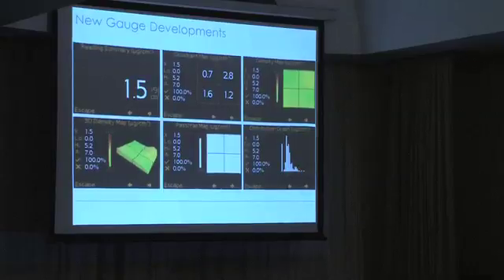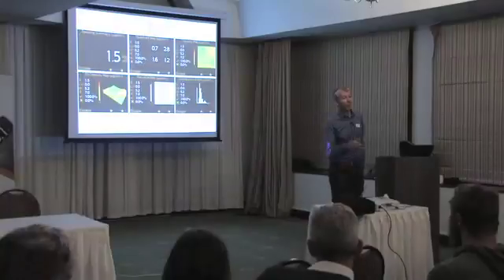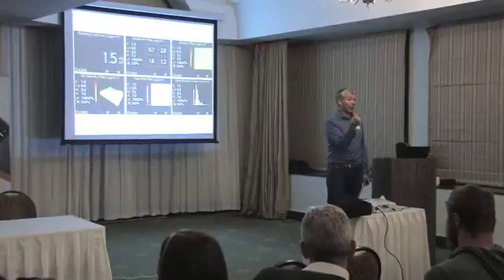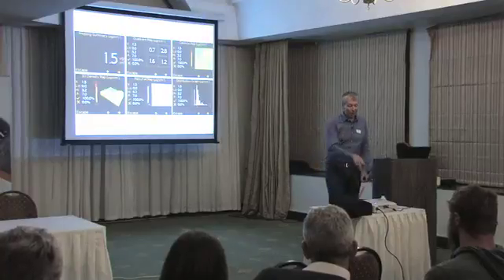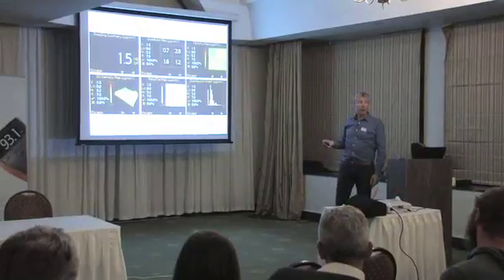If we then bump it up and add some contamination onto the surface, in this example, which is a repeat example, you will see from the 3D image that all I did to create this, and this is a bit of a cheat, is I lifted the lid of the gauge and just put my finger quickly on there. That doesn't mean that I'm a very dirty individual. Well, it might. But what it means is that our skin's very salty. Even when you come out of the shower, you can't stop your skin getting salty. And so just by touching it for a couple of seconds, you get an immediate bump in that area there.